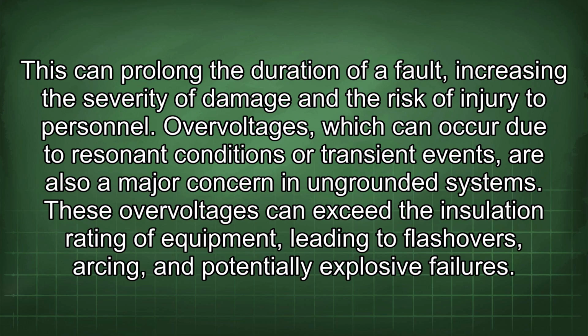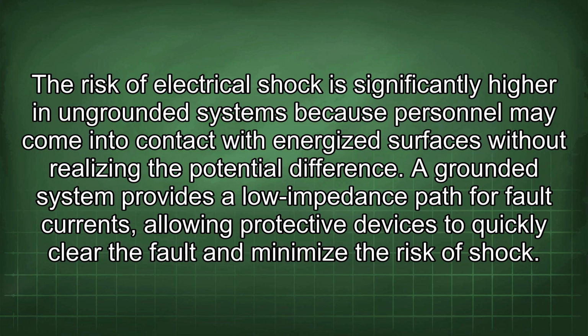Overvoltages, which can occur due to resonant conditions or transient events, are also a major concern in ungrounded systems. These overvoltages can exceed the insulation rating of equipment, leading to flashovers, arcing, and potentially explosive failures. The risk of electrical shock is significantly higher in ungrounded systems because personnel may come into contact with energized surfaces without realizing the potential difference. A grounded system provides a low impedance path for fault currents, allowing protective devices to quickly clear the fault and minimize the risk of shock.